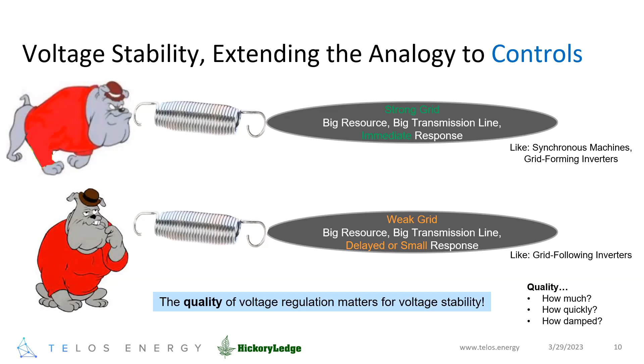So this is the concept of response time, which is really important. You need to not only be responsive in regulating voltage, but do it in a time that matters, in the relevant timeframes. This frames up the argument that it's the quality of voltage regulation that really matters for voltage stability. By quality, I mean how much effort you're putting in, how quickly you're doing it—you can't just crank up your control gains to get there—and how well damped you're doing it.